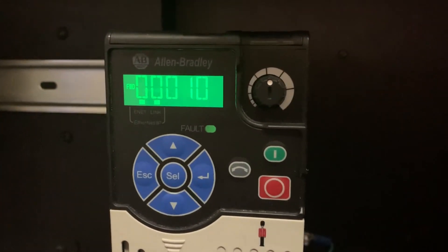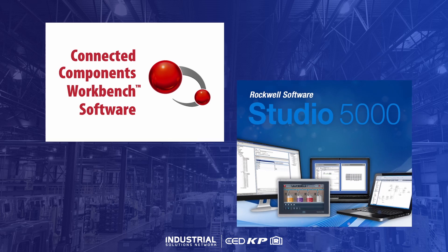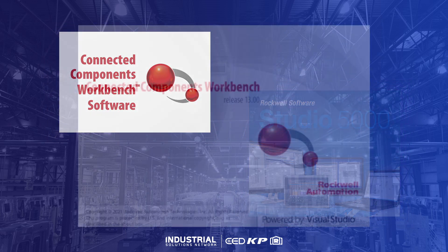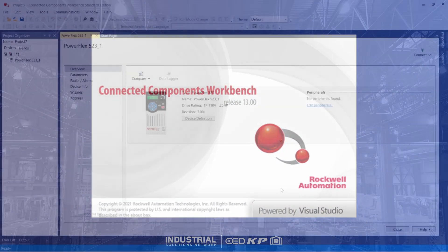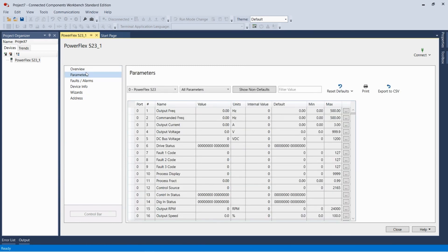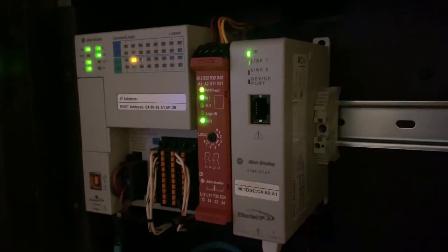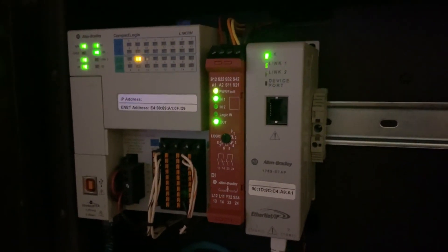Not only is the 520 a rich resource of fault data, but associated Rockwell software makes accessing this data even easier. Connected Components Workbench software is a free offering from Rockwell Automation and is the official configuration software for Rockwell Drives. CCW can easily display fault data and can even send such data to a CSV file for ease of processing. If a PLC is in play, the same fault code data may be accessed using Studio 5000.